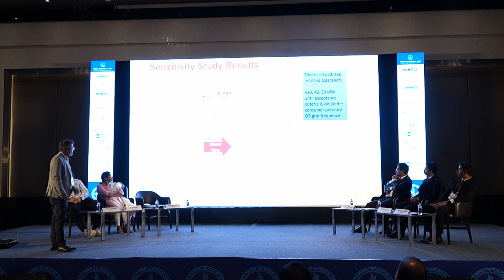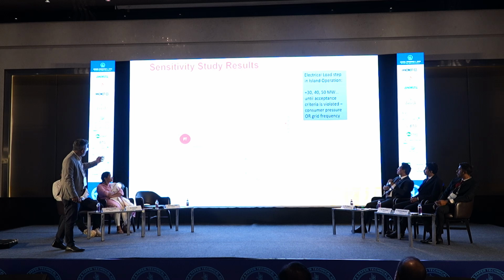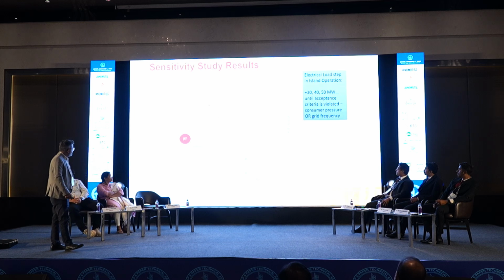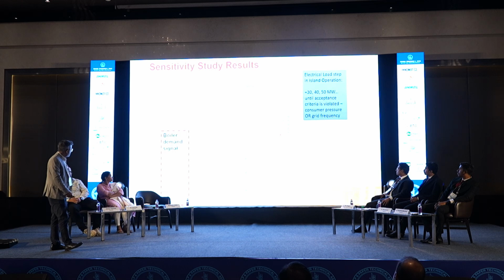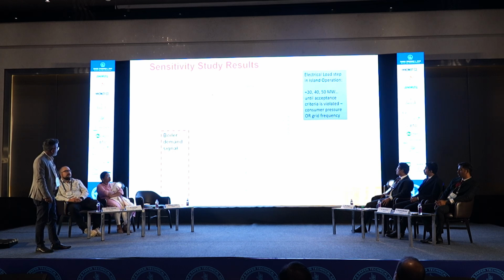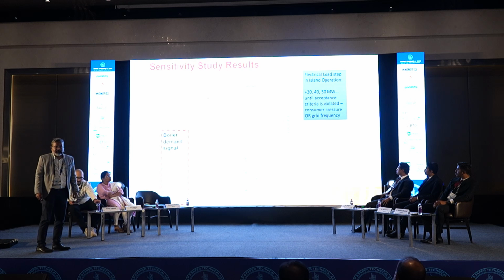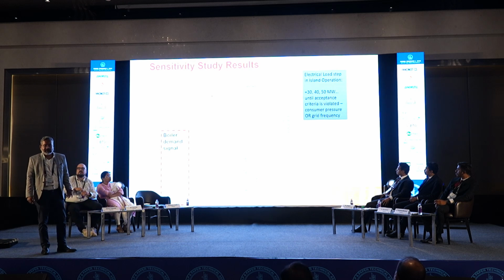So it roughly takes about 60 minutes to stabilize the header pressure. Then we see how the header pressure gets stabilized. Obviously there is a largest dip for the 70 megawatt load steps. And this is how the boiler demand signal is performing. So for 70 megawatt load steps, as you can see here, my boiler is almost going from 84% to 100%. So they are getting saturated at that level.